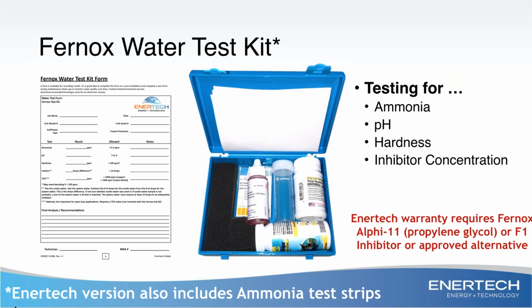You may have to add some inhibitor over time. The Fernox product is very, very easy to use. You can't really overdose the inhibitor. It corrects for both high pH and low pH. If you add a little bit too much, it's not going to hurt anything. So it's very, very easy to maintain, but the key is making sure that you test that water. This is really cheap insurance.